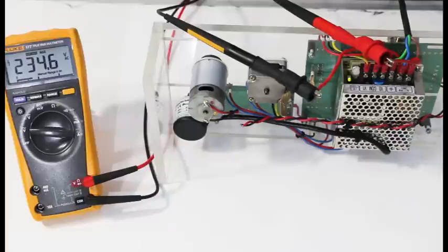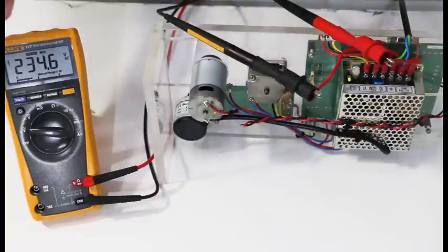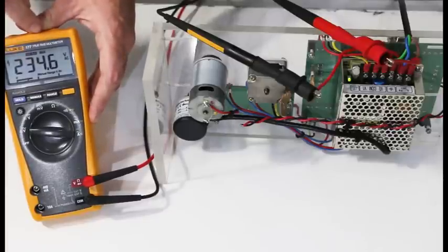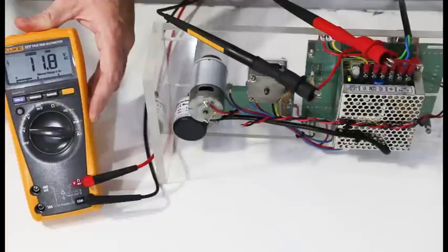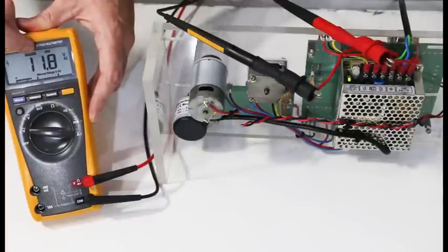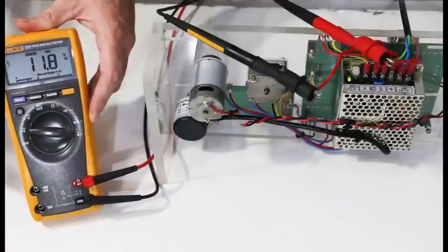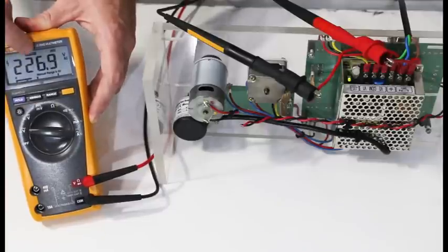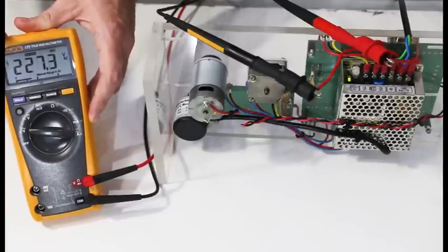If I switch off my system, you can hear the meter makes a few beeps. It's basically indicating to you that it has new values that it's monitoring. If I look at my maximum value, I have 234 volts. If I go to my minimum value, here I have 11.8. This is an indication to me that my voltage has dropped off during some point of the measurement. If I press my average, that is my average voltage over time.